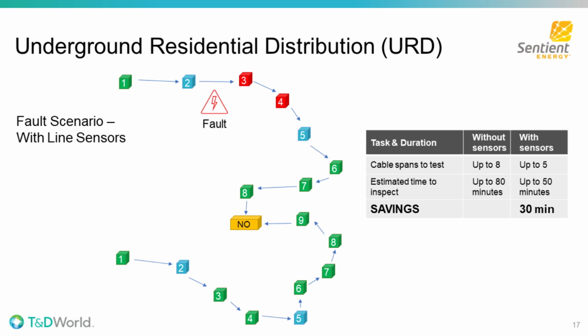So again, with a few sensing locations, you can save several stops for the crew. And let's say a URD stop takes 10 minutes instead of 15, which we used on the feeder. That means you're going to cut your maximum fault finding time from 80 minutes down to 50 minutes, shaving off 30 minutes. So you can see you can save just as much time on laterals as on feeders, especially laterals with lots of transformer cabinets.